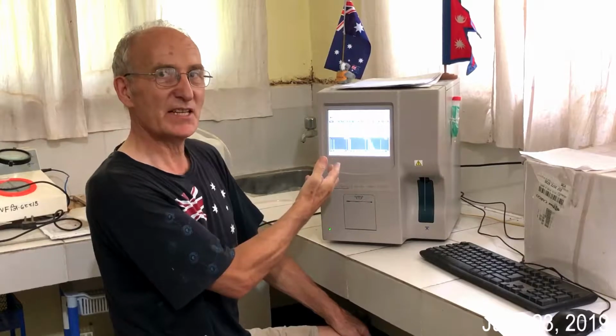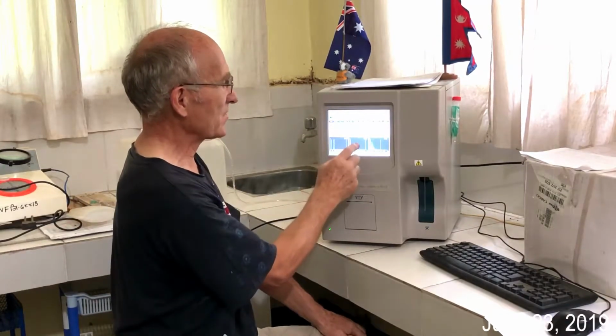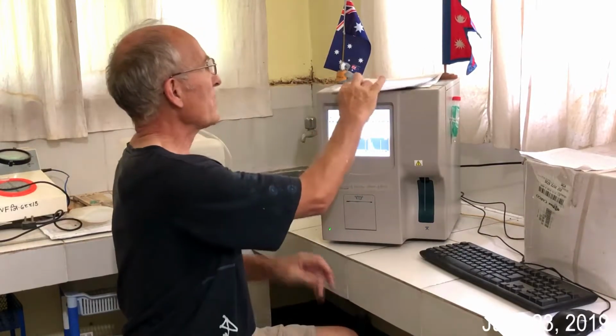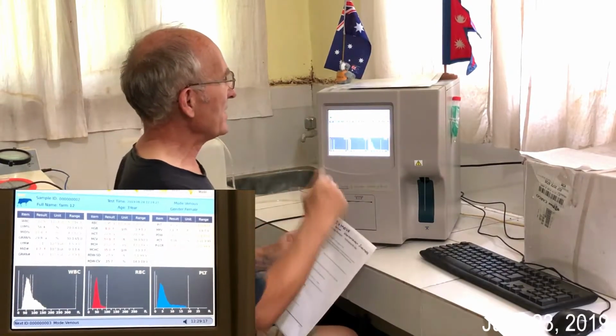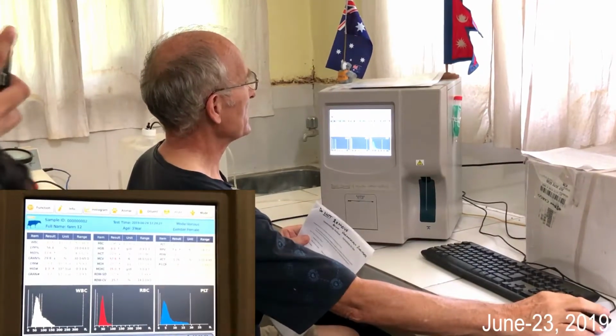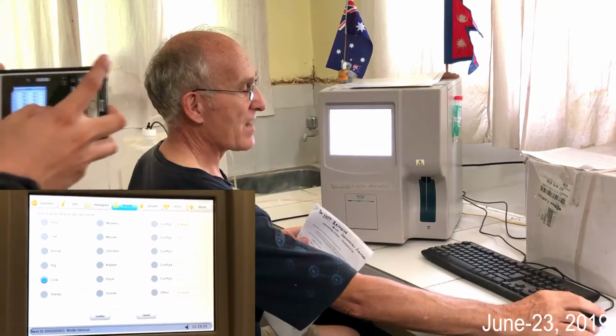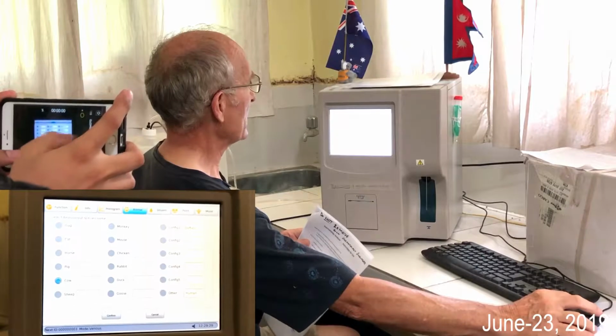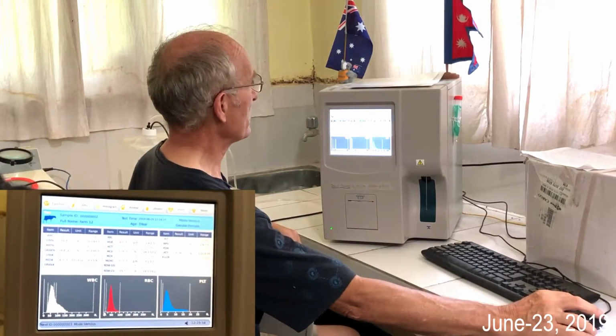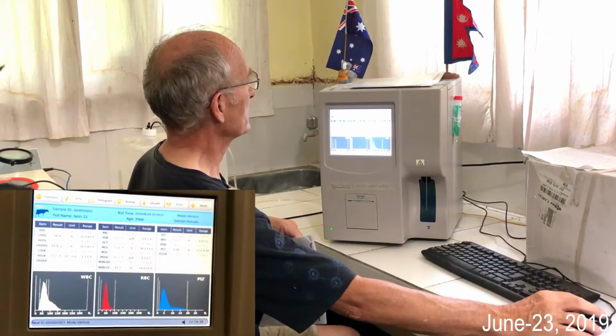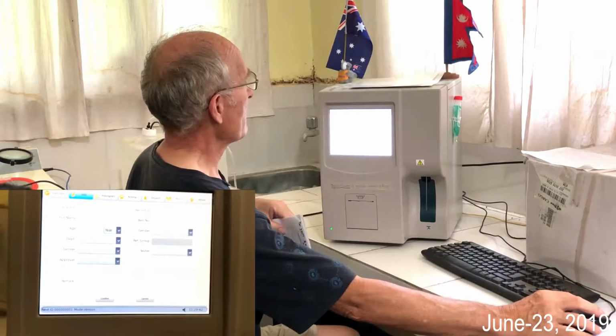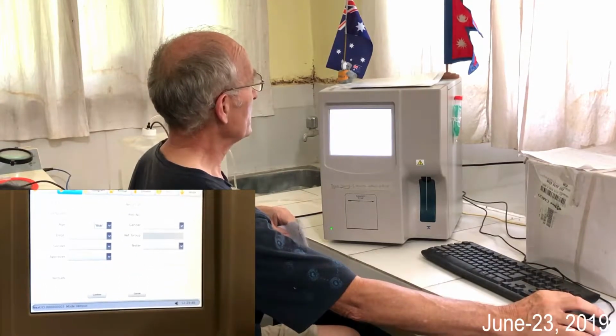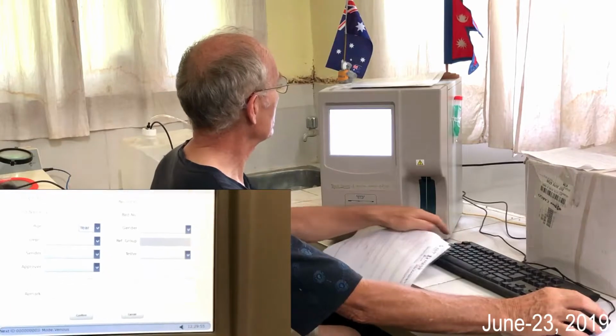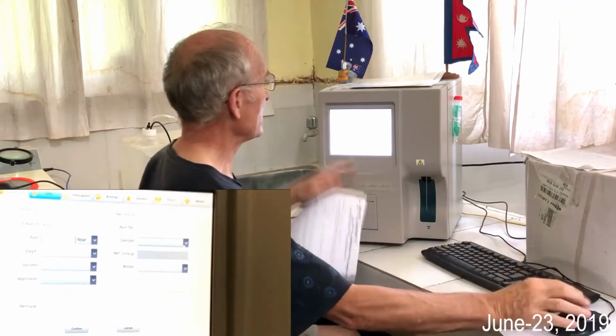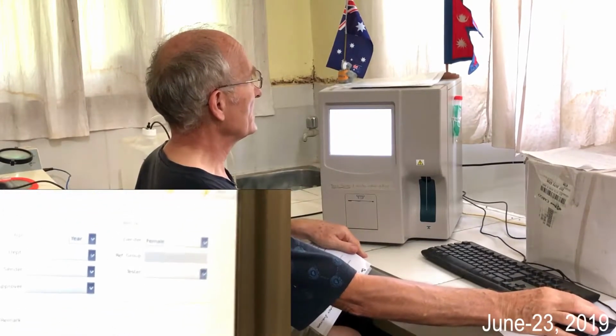Okay, so now the machine has initialized and we see on the screen white blood cells, red blood cells, platelets. What we need to do now is, following the instructions that are on here, enter the animal details. So we go to the top, in the center, click animal, and the sample that we have is a bovine. So we come down here to cow, we select cow, and we come further down to confirm and select confirm. So now we have it's a cow. We click information because we want to identify the sample. So the name of the animal is Kali, K-A-L-I, and it's Kali 1. The age is 7 years. We type in 7, it's already given us the years. The gender is female.